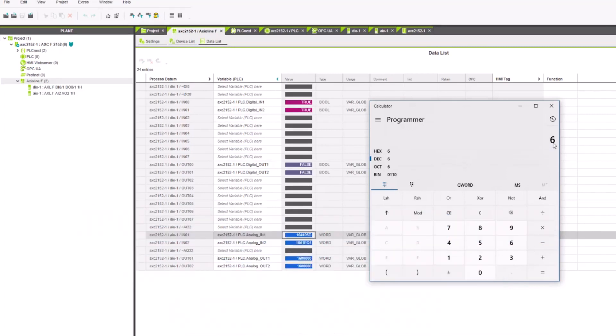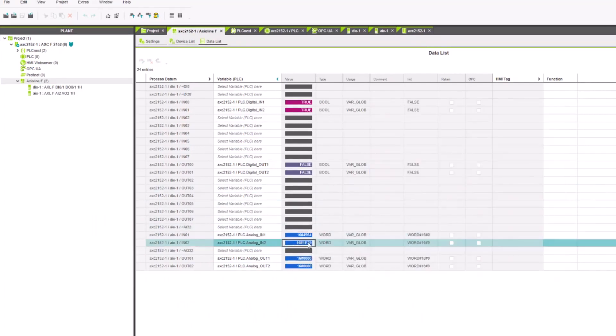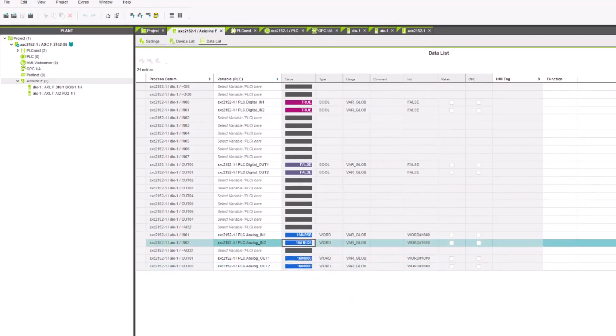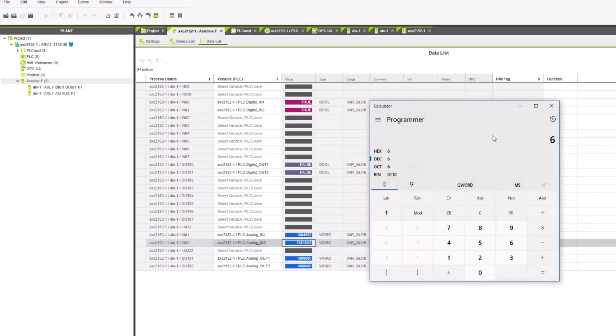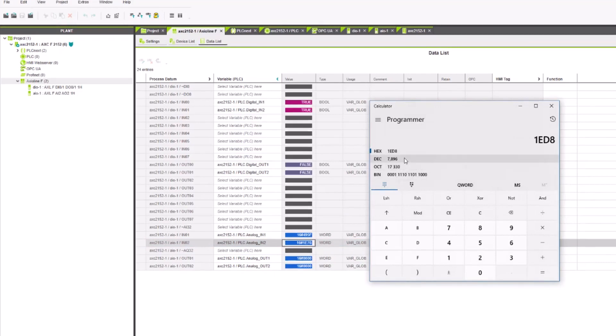So let's just divide that by 3,000. And it should tell us that we have about 6, well, exactly 6 there, set on the potentiometer. If we take the temperature input, so 1ED8, we're sitting at about 24, 25 degrees. So if we put that in, go back to hex, and you can see that that is 7,896, and if we divide that by 3,000, oh, it's rounding up because it's in programmer mode.